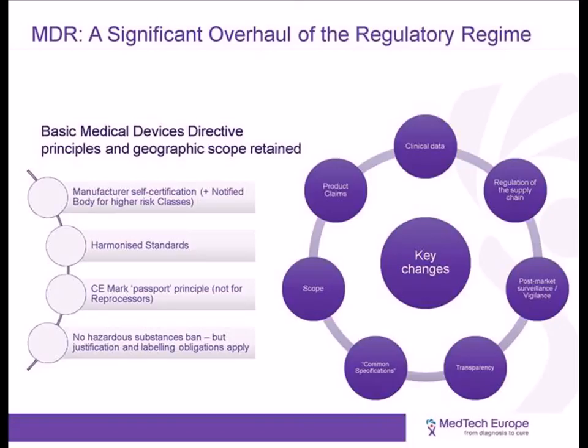Transparency is another significant theme in the MDR. Final reports of clinical investigations, plus summaries of those reports, will be publicly accessible in EudaMed, the new EU medical devices database. Commercially sensitive and proprietary information might therefore be in the public domain via EudaMed, unless the need to keep the information confidential has been duly justified.